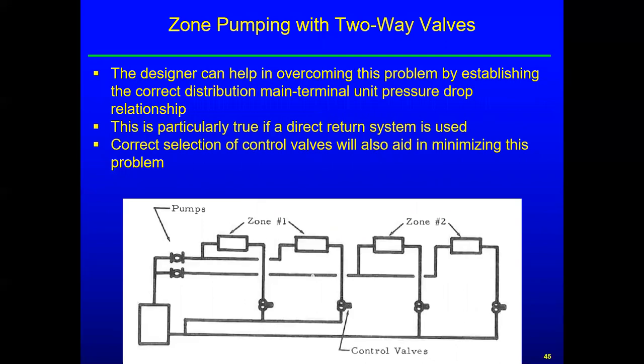This goes back to the zone pumping. I kind of talked through this before. This can reduce the number of zones on a particular pump. That can be a small pump, and so that can help. That's especially true of direct return, because the zone two units have longer supply and return. Zone one units are both fairly short, so that helps in that regard as well. And of course, if we get our pressure drop correct on our control valves, this will aid in minimizing the balance and imbalance problem.